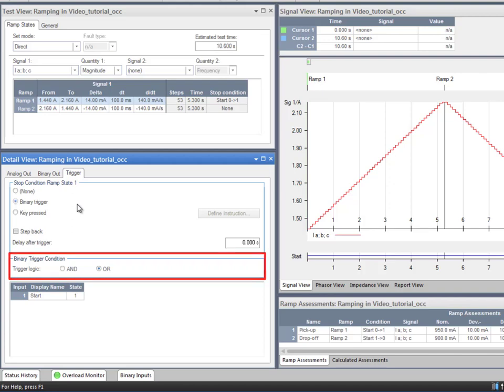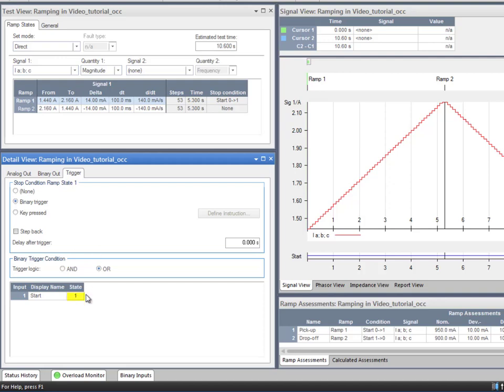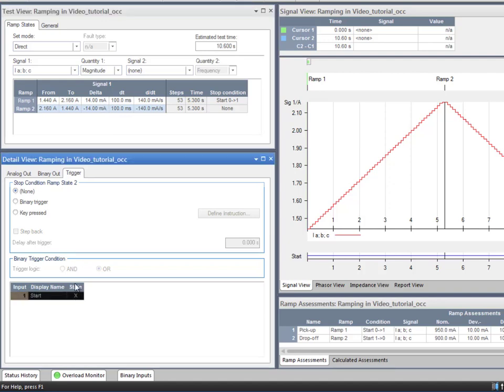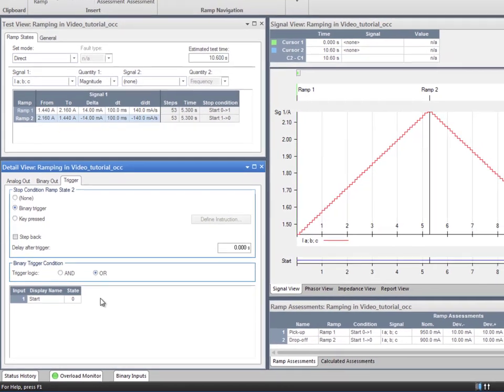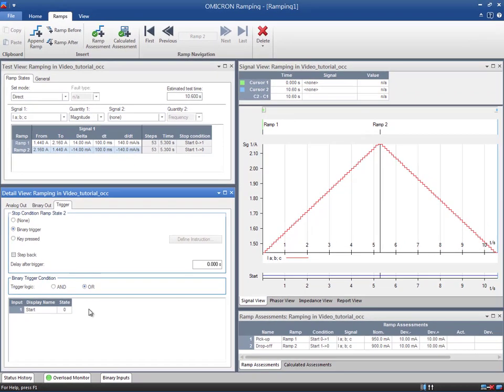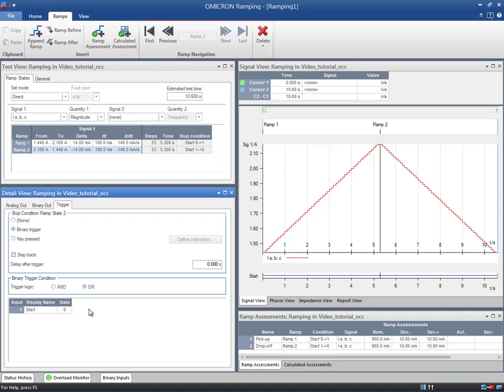The binary trigger can be any single binary input of the CMC or a logical combination of multiple binary inputs. The logic functions AND and OR are available for that purpose. In the binary trigger condition box, you need to specify the binary inputs you want to use. In our example, the first state must stop when the start signal switches to 1, while the second state must stop when the start signal goes back to 0. Note that the detail view needs to be configured for each state. Toggle from one state to the other by clicking the arrows from the ramp navigation toolbar or directly selecting the specific state.